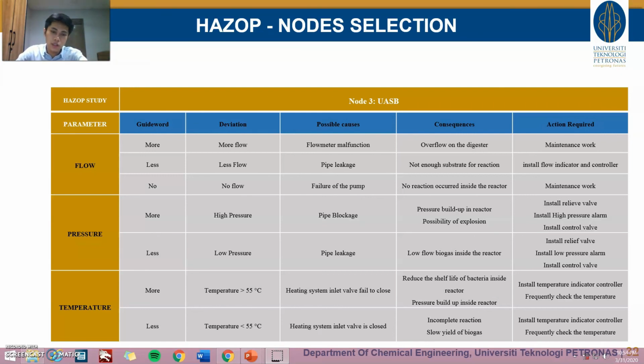For temperature below 55 degrees Celsius, the cause is the heating system inlet valve is closed. Consequence, incomplete reaction, slow yield of biogas. Action required is to install temperature indicator controller and frequently check the temperature.